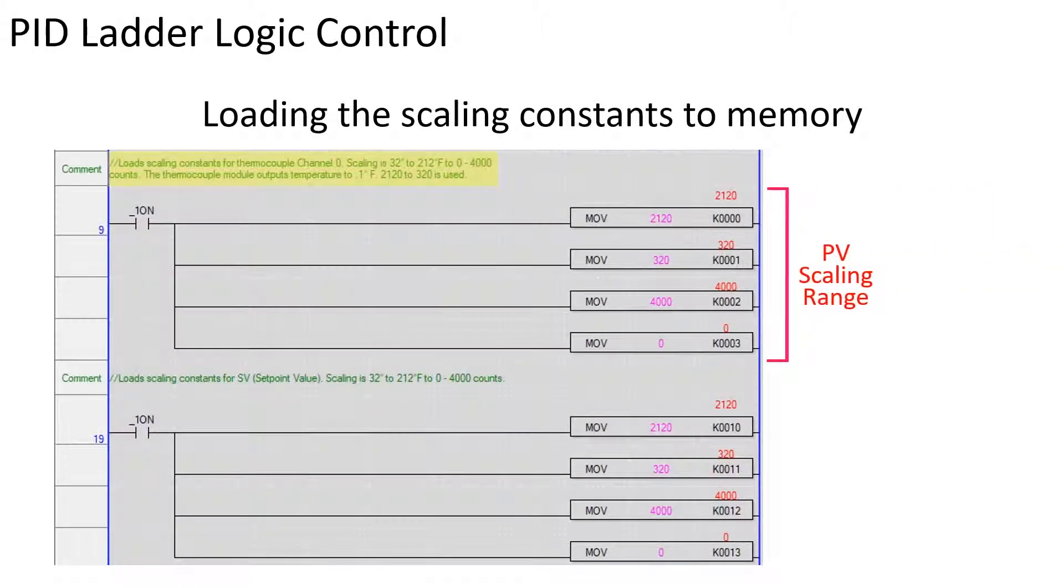The PV scaling is 32 to 212 degrees Fahrenheit. This range is scaled for 0 to 4,000 counts. Ladder rung number 9 loads the constants for scaling the PV. These constants will be used to scale the PV temperature range to the analog counts.